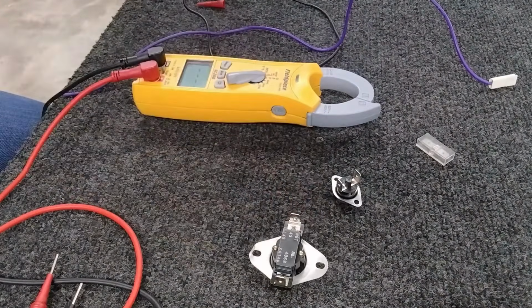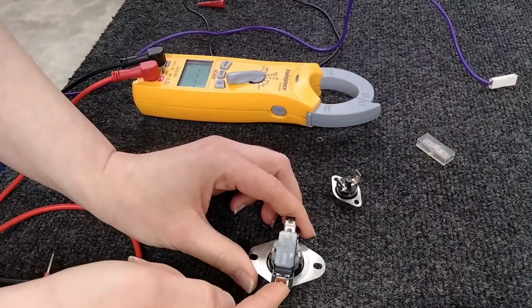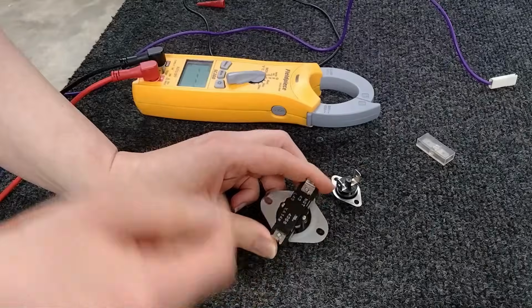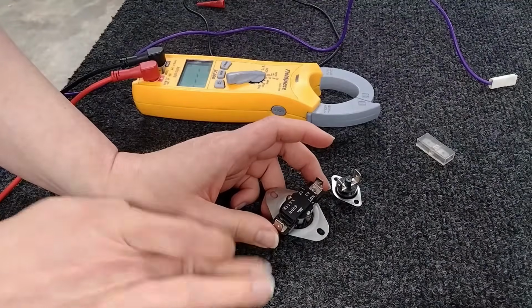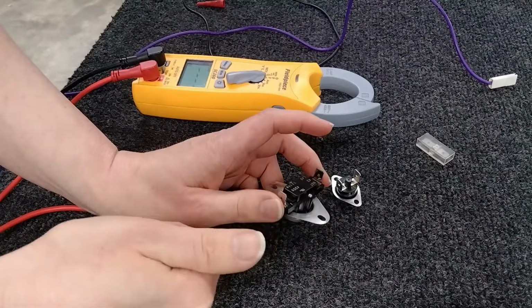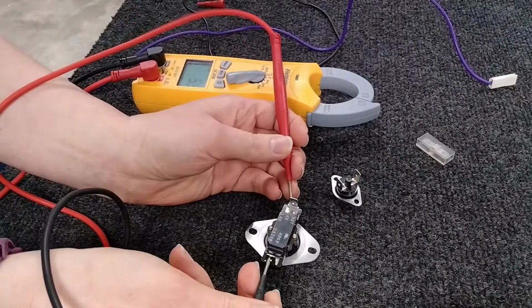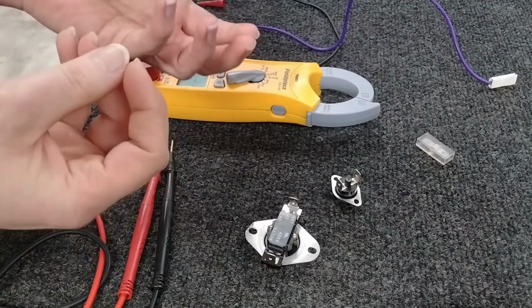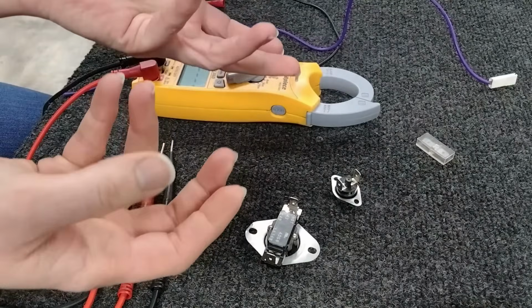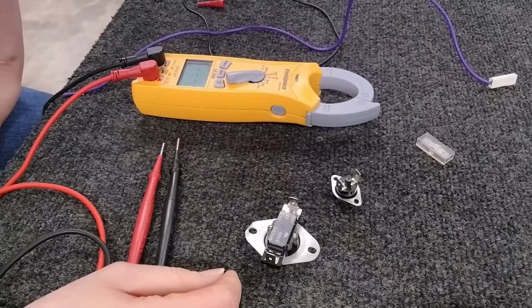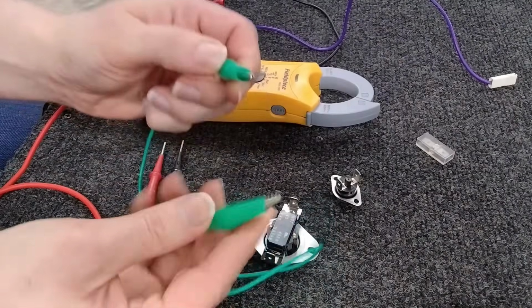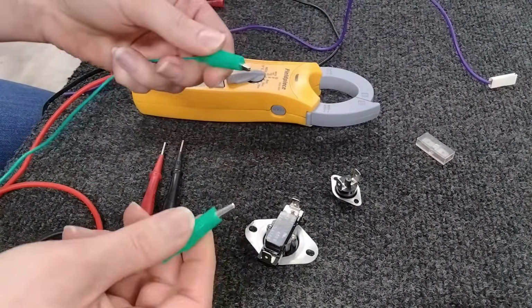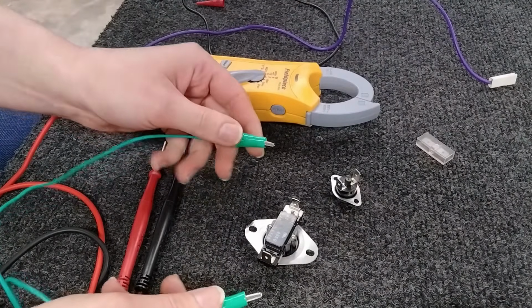A common way that techs do this is, these are going to be normally closed, which means voltage is going to go through. It's going to have no resistance, so it's going to go through all the lines to the board and tell the board all systems go. A way to get around that, just to see what's going on, is if you're testing it and you're getting continuity, but you're still getting, say, the board blinking and telling you open limit switch. Fortunately, there's some models, I know of a few Lennoxes that will just say open limit switch, but it won't tell you which one. You can use these little gator clip guys to jump around it, or in a minute, I'll show you how to heat test it and see what it does.